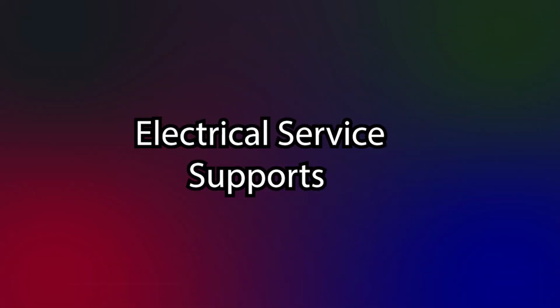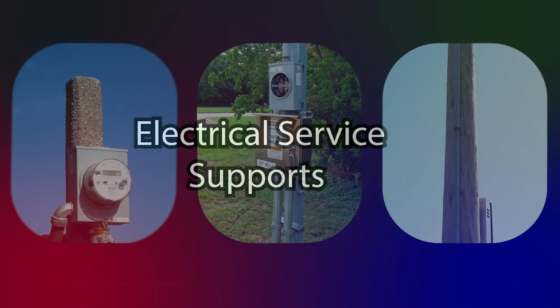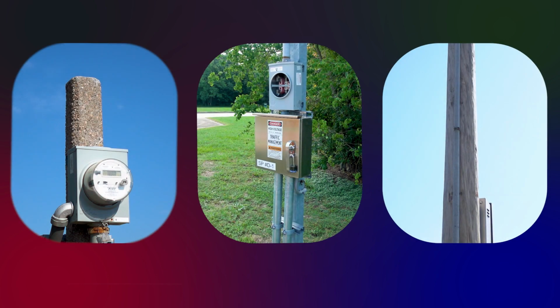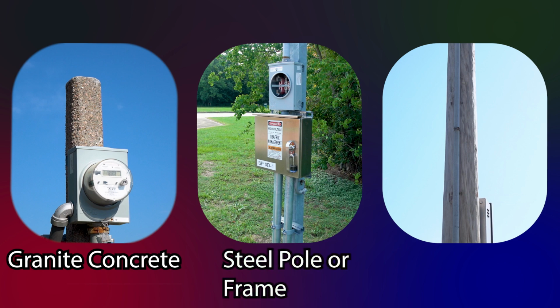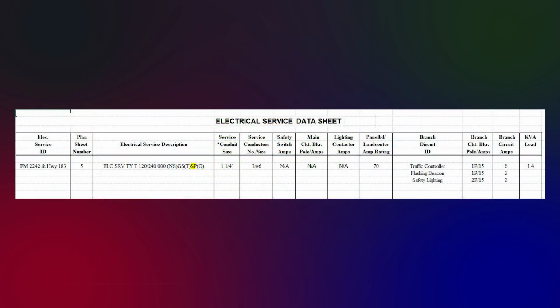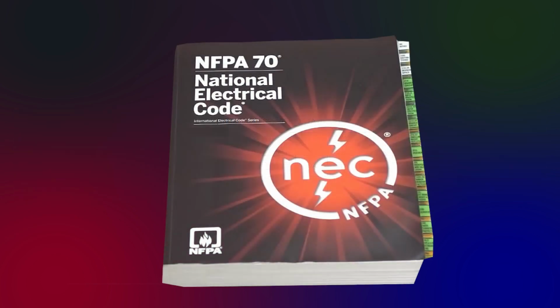Now, let's discuss the mounting of the Type T service. All service equipment is mounted to a support structure, either a granite concrete pole, a steel frame, or a treated timber pole as specified by the service data in the plans. In this project's electrical service data chart, the design engineer has specified a steel pole service support, designated SP. The NEC provides us with several references when mounting electrical equipment, so let's look at them.